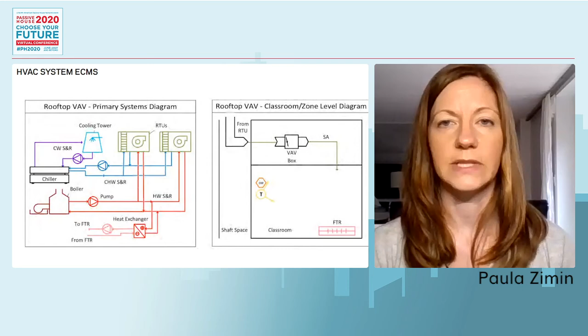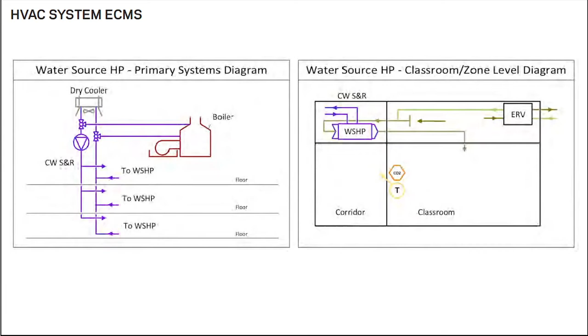So that's the SCA standard, and quite honestly, SCA has done a really good job of optimizing the efficiency of this particular system, reducing ventilation rates and fan powers associated with moving air around in the building. But we did investigate some other strategies. Another mechanical system that we investigated was a water source heat pump system. The water source heat pump system will also have a boiler, but it will have a lower temperature water loop around the building. It would have a dry cooler in this instance that we investigated. And otherwise, there's a central loop throughout the building, a condenser water loop.